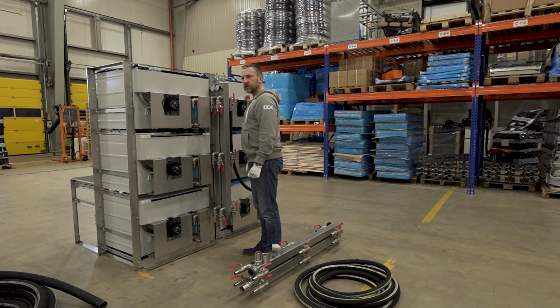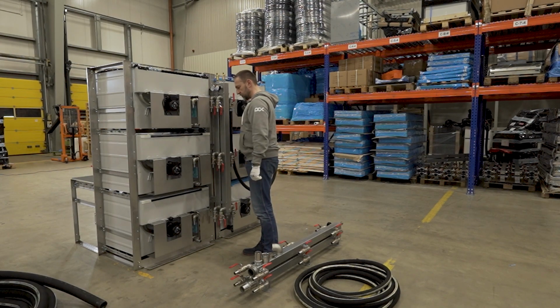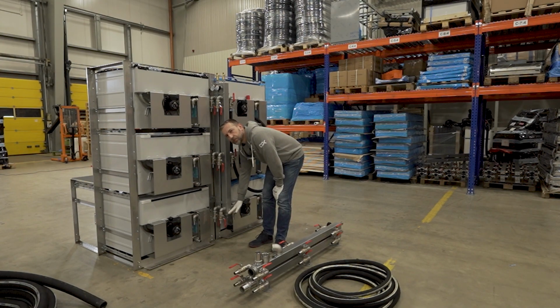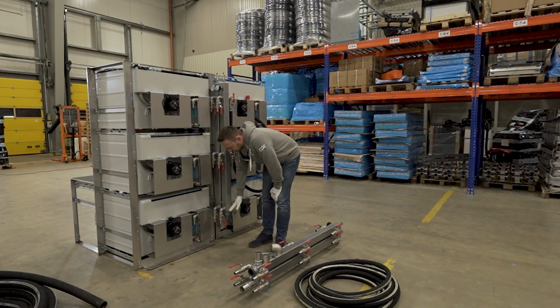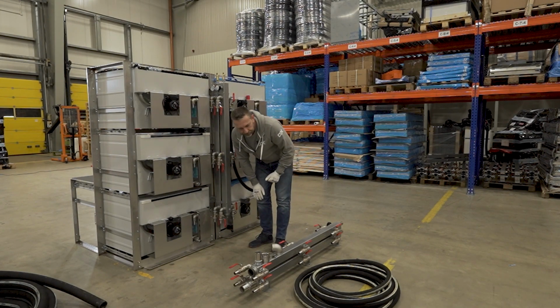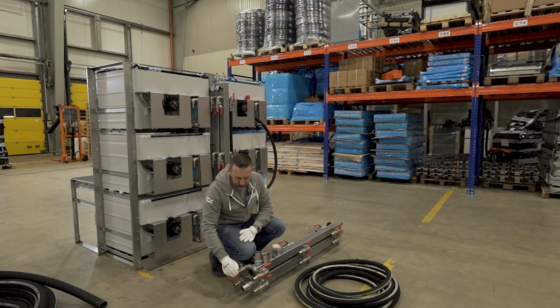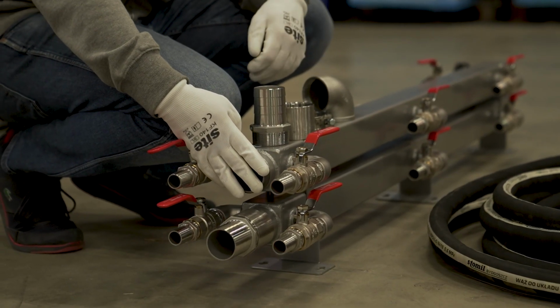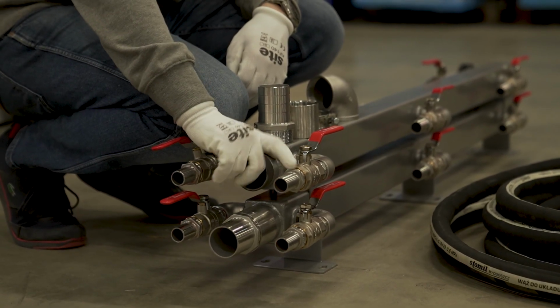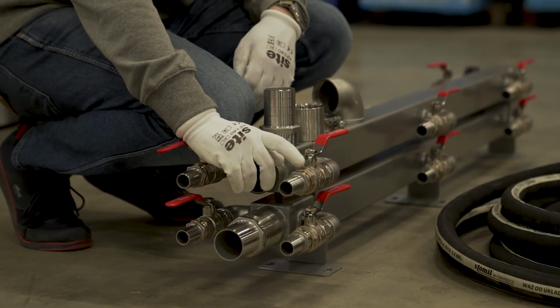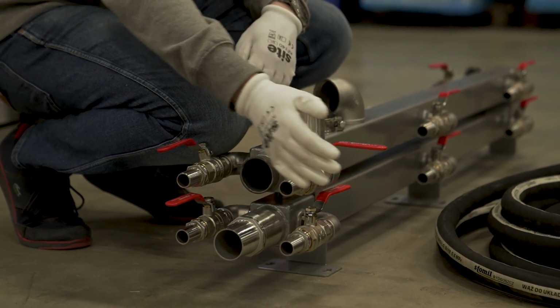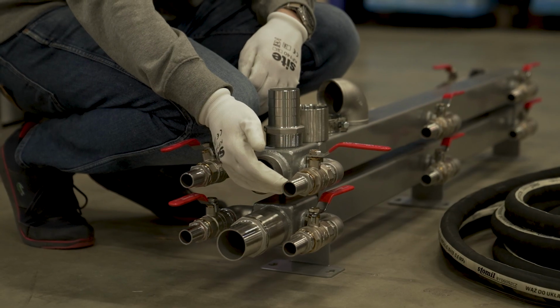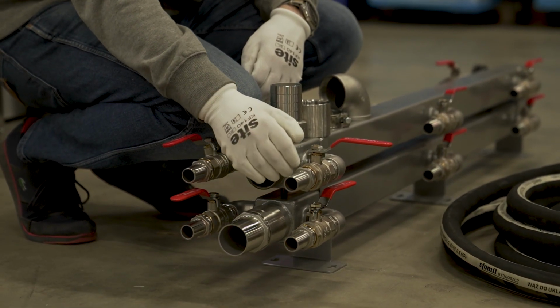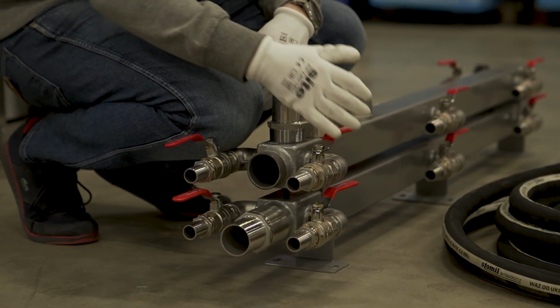So let's find out how we properly configure the manifold system, I mean the supply and return to the manifold. The supply and return is located at the bottom of the manifold, and you can attach different piping here in the way that is convenient for you. It's convenient to route the tubing correctly. I have an additional manifold here, so I will just quickly illustrate how to properly connect the tubing. The manifold is using two diameters. On the supply and return from the enclosures, we use 1 inch diameter tubing and 1 inch fitting, so 1 inch, DN 25. And as you can see here, we have valves as described, so we can basically close each specific enclosure and supply only the enclosure in which we would like to operate.